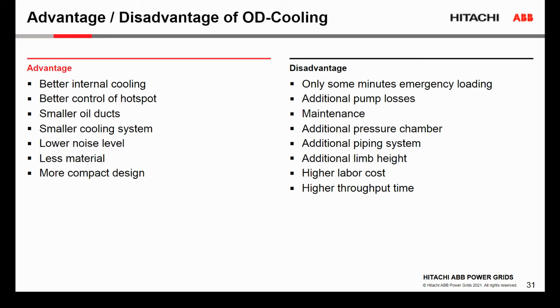So, advantages and disadvantages of OD. Normally the OD cooling is much more efficient. We can control the hotspot in a better way. We can use smaller oil ducts. We can sometimes reduce the noise level because we will use fewer fans. We can reduce the size of the transformer. We can also use less material, but we have to be careful, because if we increase the current density, we may have a problem with mechanical stresses during a short circuit.